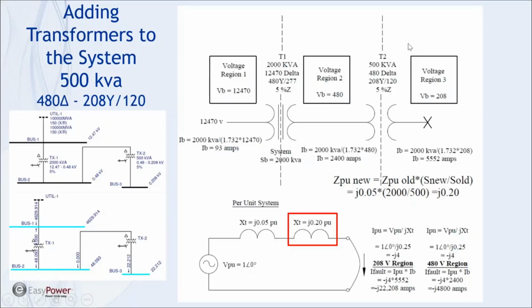But now, and I do this a lot, I'm sure many of you do it as well, when we have 480, what we don't have in a 480 system is 120 volt for receptacles and low voltage power, and sometimes lighting as well. So it's real common to have another transformer here. I just started this process by taking a 500 kVA transformer, and that is 480 to 208. On a 500 kVA transformer, that's a lot of current. It would actually take a very large panel board on this side to take advantage of the full load rating of the transformer here. But this is just an example.